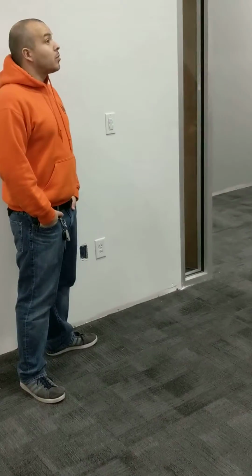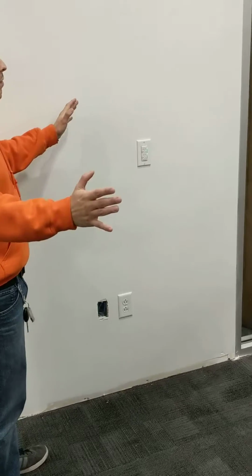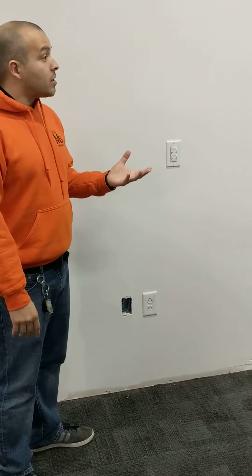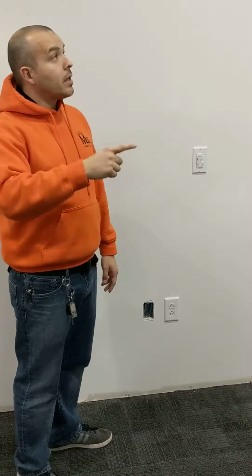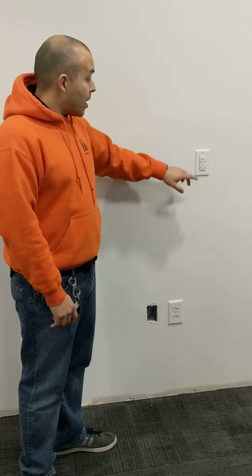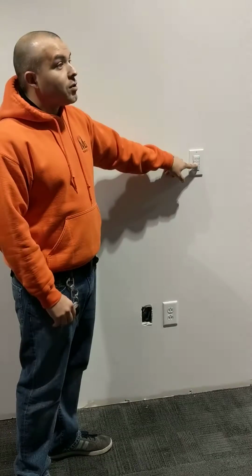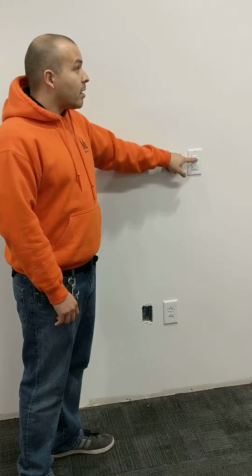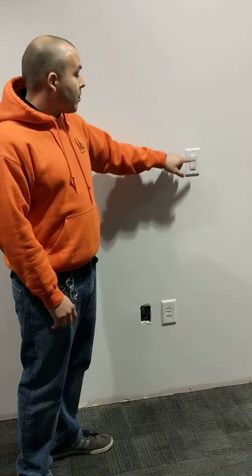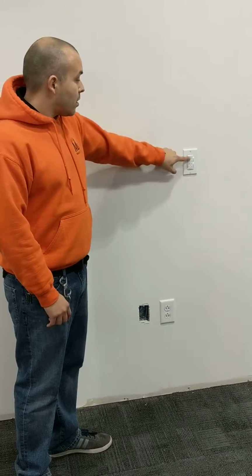This is going to work similar to how everything on this half of the open office is going to. It's all set up as dual pole setup rooms. So you're going to have your 2x4s or 2x2s as your pole 2, and your can lights are going to be your pole 1. Since 99% of the time you're just going to walk into a room and hit the on switch, I paired everything to the top switch. So they all turn on and off the top switch. The bottom switch itself is just turning off our 2x2s or 2x4s. So if you want just the can lights to be on, you turn on the top light and then off the bottom. If you only want to turn on your 2x4s, you only hit the bottom.